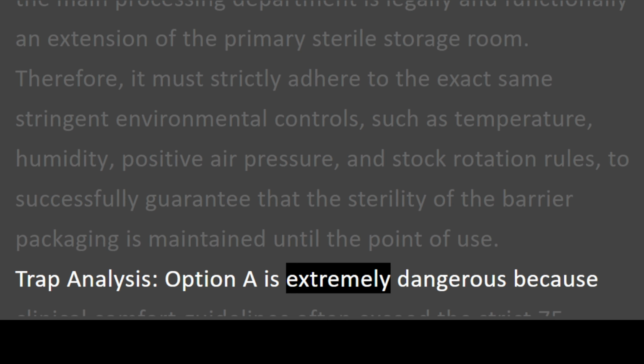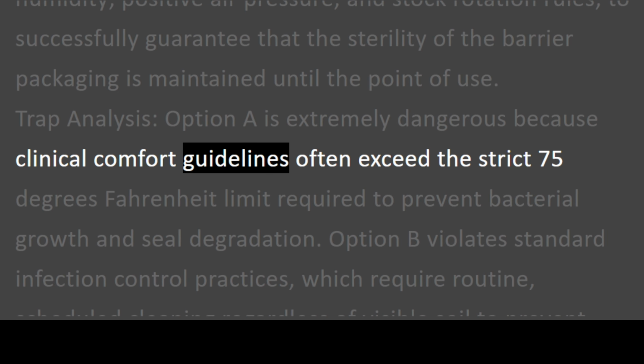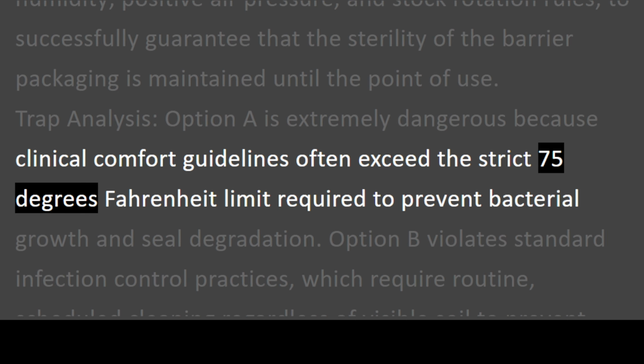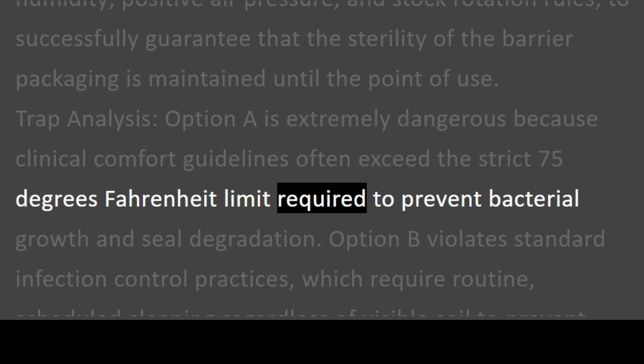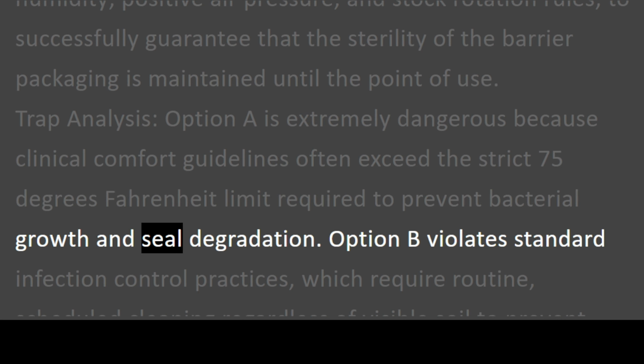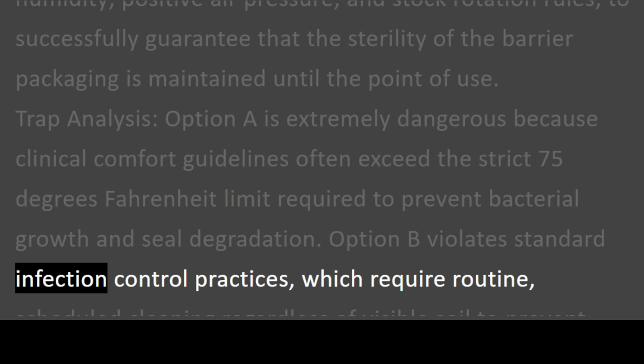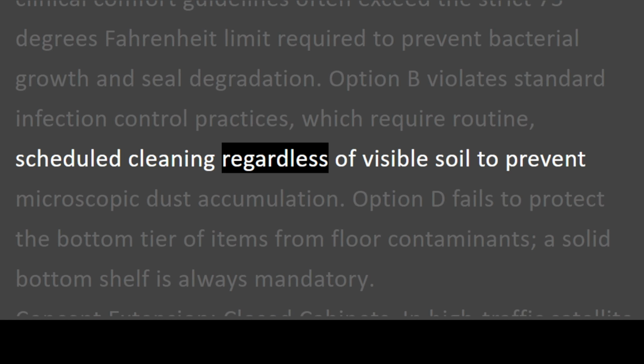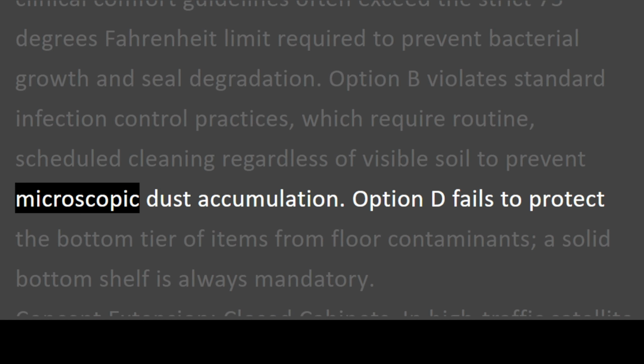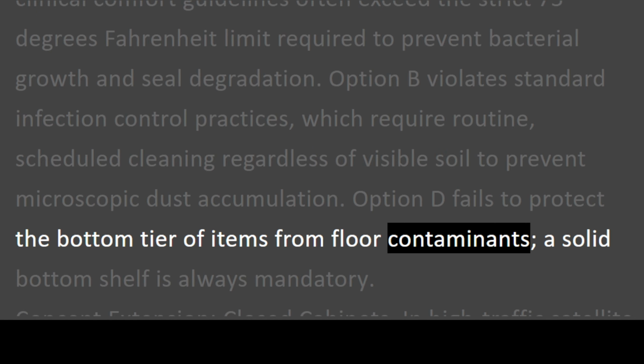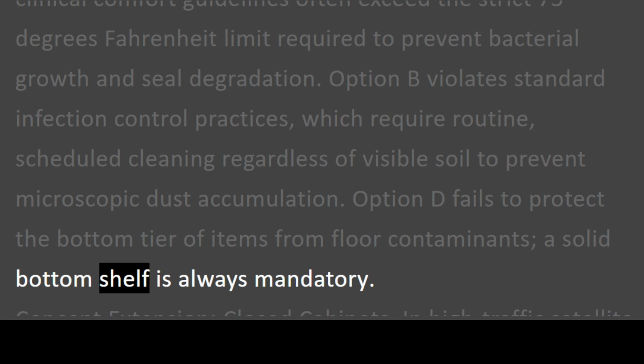Option A is extremely dangerous because clinical comfort guidelines often exceed the strict 75 degrees Fahrenheit limit required to prevent bacterial growth and seal degradation. Option B violates standard infection control practices, which require routine, scheduled cleaning regardless of visible soil to prevent microscopic dust accumulation. Option D fails to protect the bottom tier of items from floor contaminants. A solid bottom shelf is always mandatory.